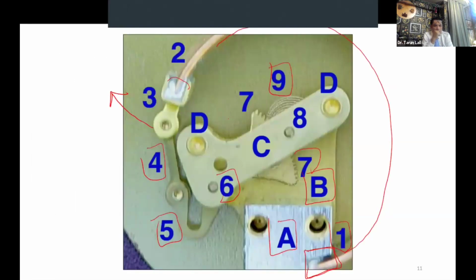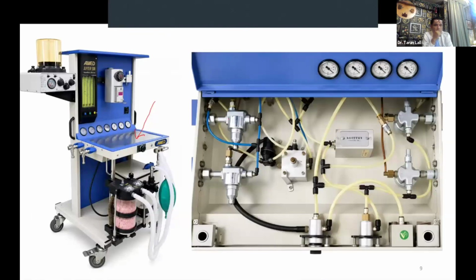The next structure in the high pressure system. What we have seen is that this is the high pressure system. You can see here that somewhere here would be the cylinders. Of course, that is the high pressure system connected through the pin index system on the yoke assembly. This is your pressure regulator, and this copper tubing that you see here is what is taking the pressure to the Bourdon gauge. So I have covered the Bourdon gauge. Now let us see how a pressure regulator works. Then we will come to the other connections in the high pressure system.